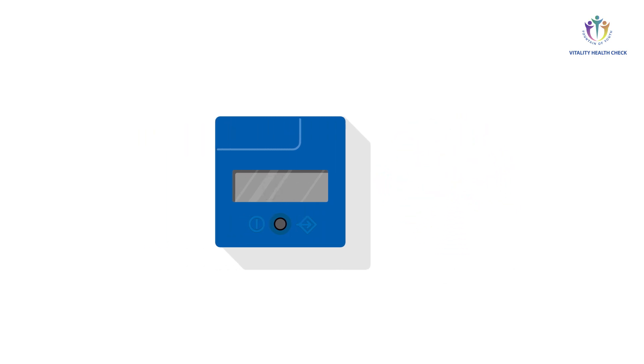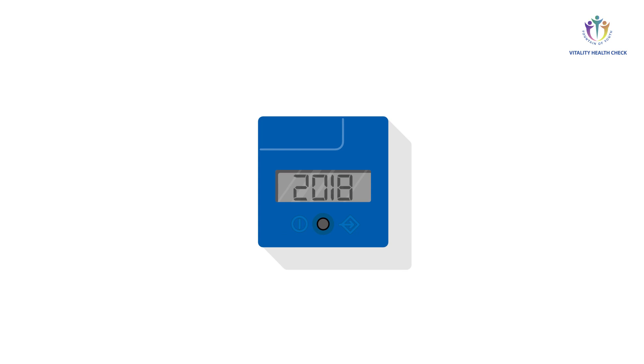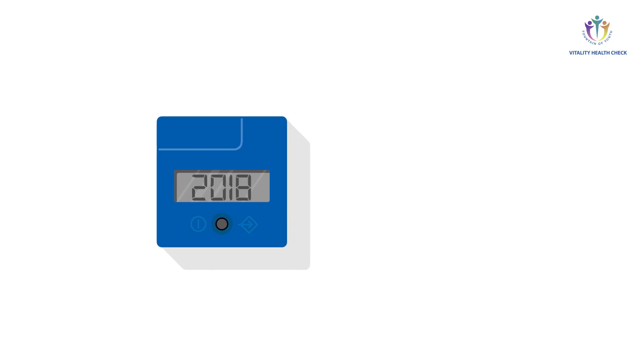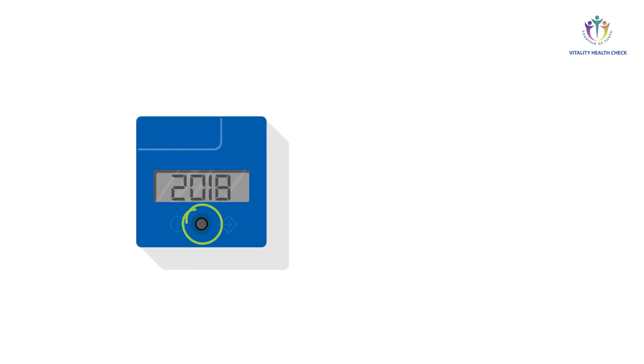The display will switch and show the currently stored date in the sequence year, month, day, hour, and minute. Accurate date setting is important in order to control whether the test cassette has reached its expiration date.